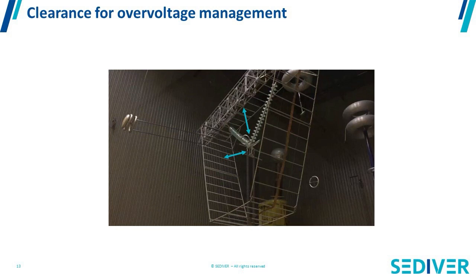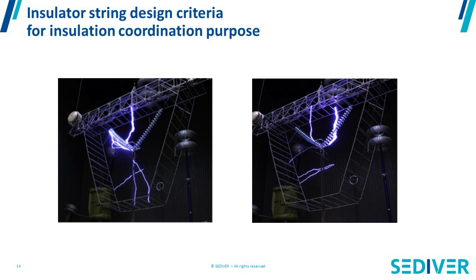You will define this distance for a number of reasons: insulation under different conditions, and the possibility for maintenance workers to climb the tower and go around the conductors without being in danger. This is what we call live-line work, and for that you have minimum approach distance rules which exist for each type of line. Overall, this all contributes to the definition of a distance between the conductors and anything that is grounded — typically the tower. This clearance is determined by several different physical properties.